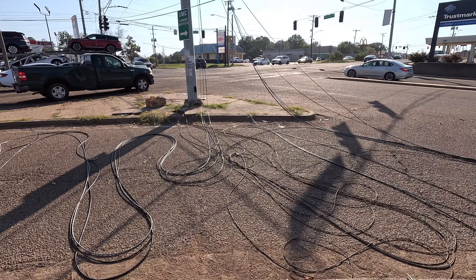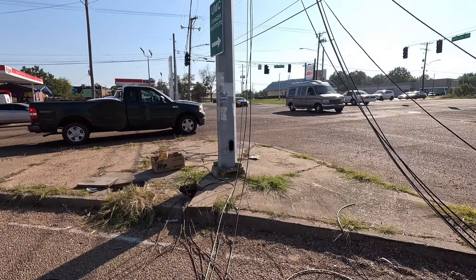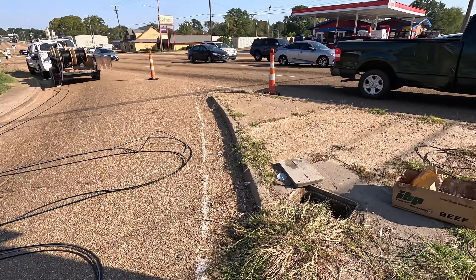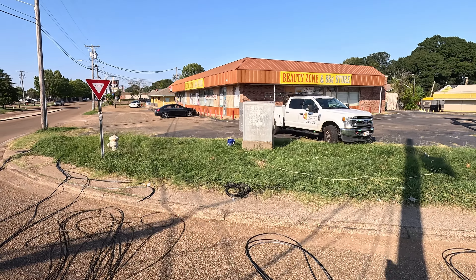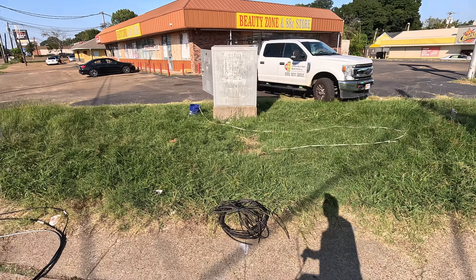I won't really be able to get this cable down and over. Pretty much coming down to just the eight or seven conductors that are in there now. But these poles, they've got trash in them, junk in them — I don't even know what some of this is. We could possibly make enough room, but we're adding in thicker, bigger cables, and our weather head's pretty packed. The bottom is already cut out — the plastic's cut out to have all that fit in there. This mule tape is going in pretty smooth, and it's out already.